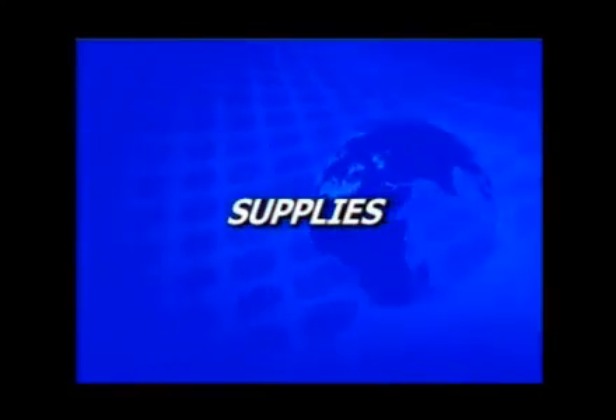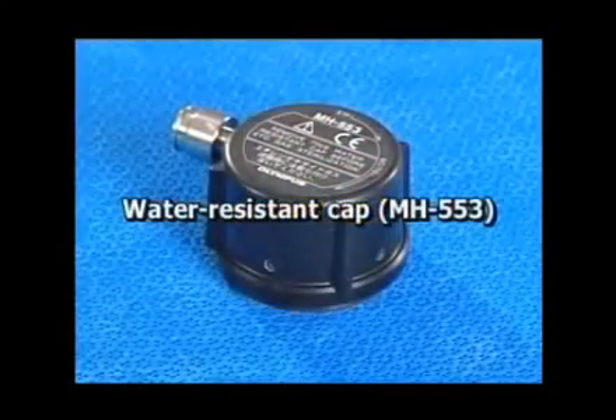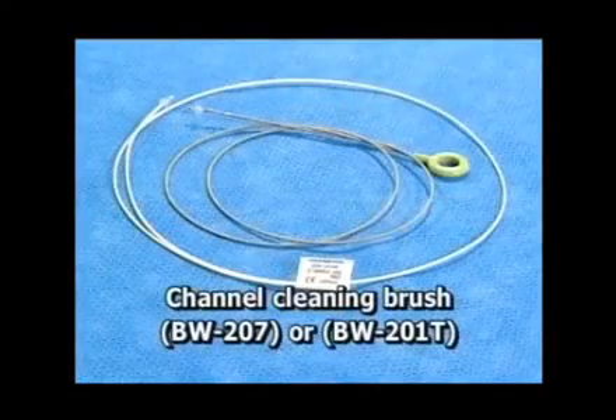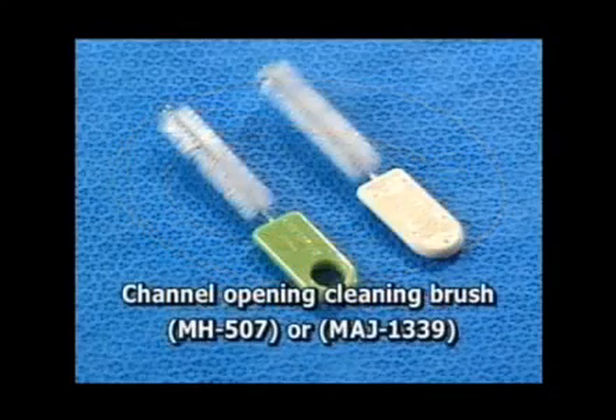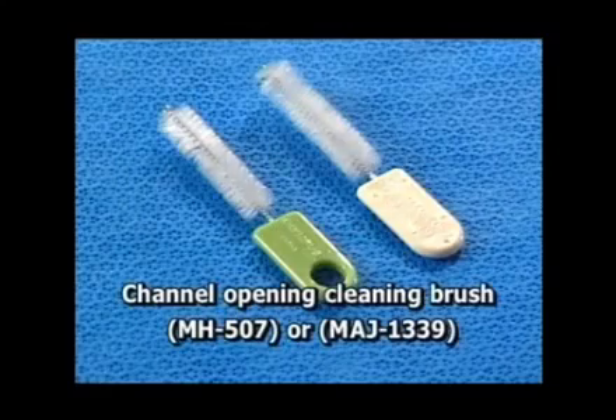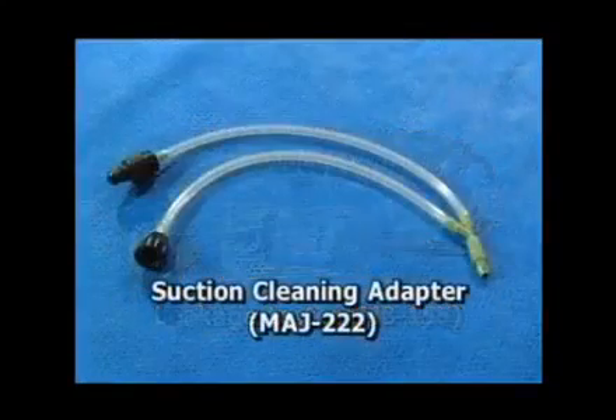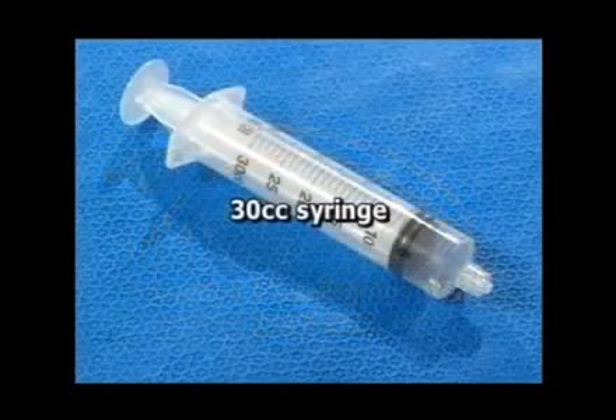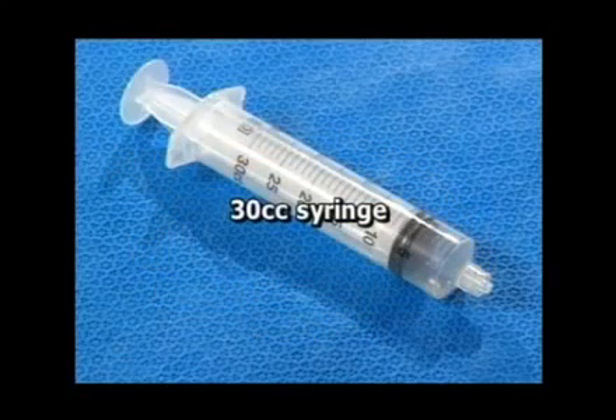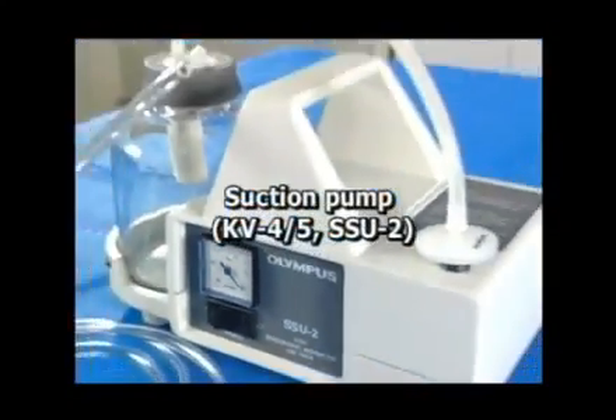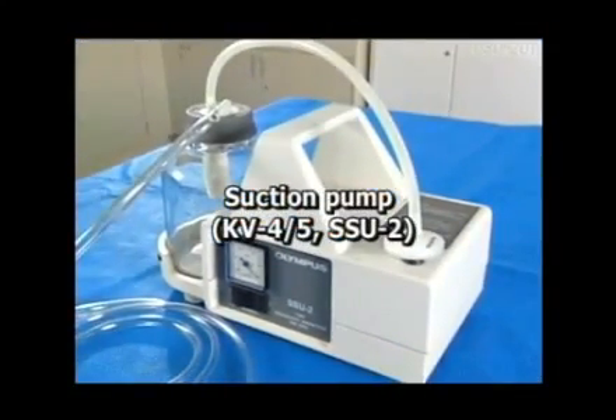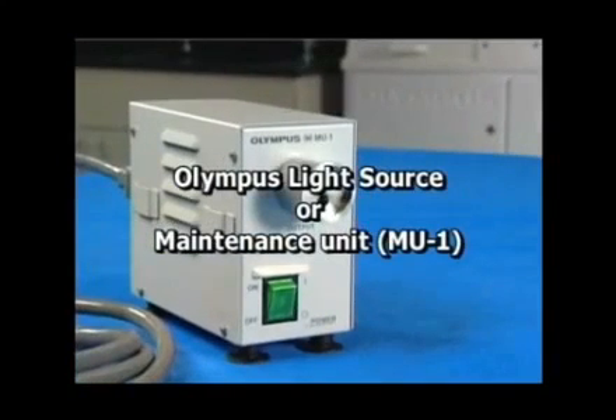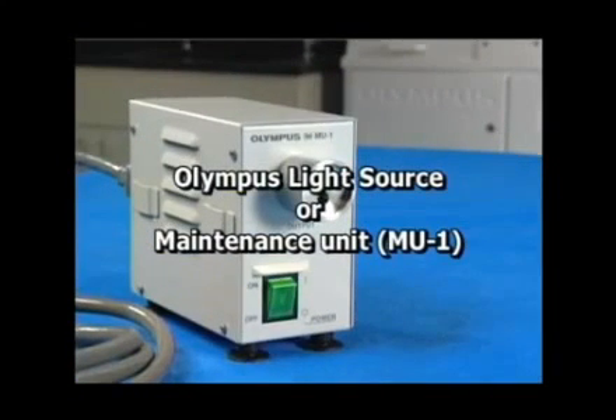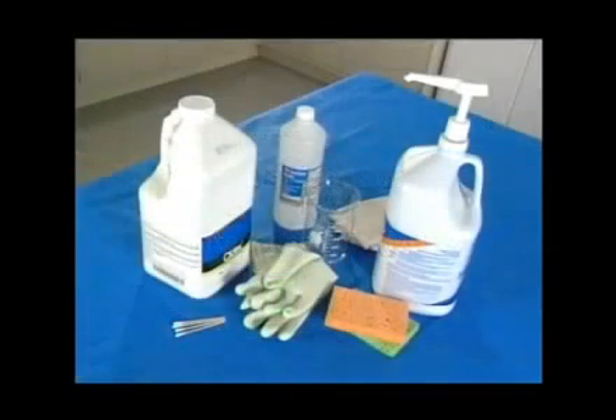To perform the reprocessing procedure, the following Olympus reprocessing accessories will be needed: a water-resistant cap, a reusable or single-use channel cleaning brush, a reusable or single-use channel opening cleaning brush, a leakage tester, a suction cleaning adapter, a 30 cc syringe for injecting reprocessing fluids through the endoscope, a source of suction to aspirate fluids through the bronchoscope, and either an Olympus light source or maintenance unit to provide a source of air for leakage testing. Consult your bronchoscope's instruction manual for a list of required general supplies.